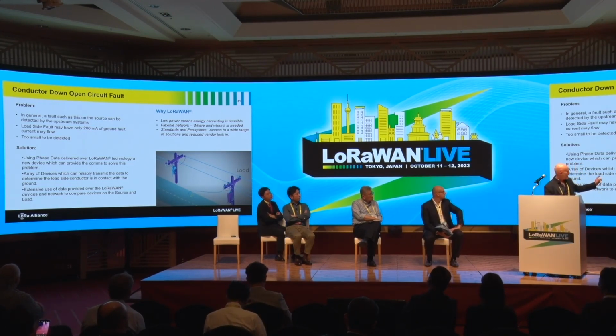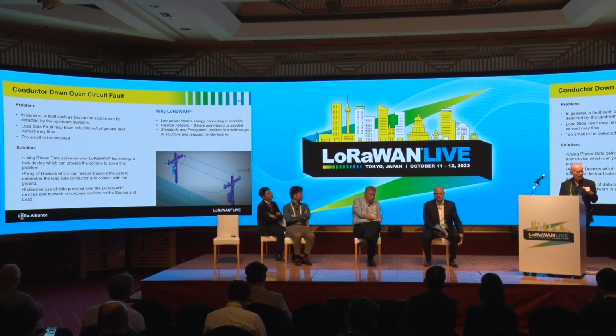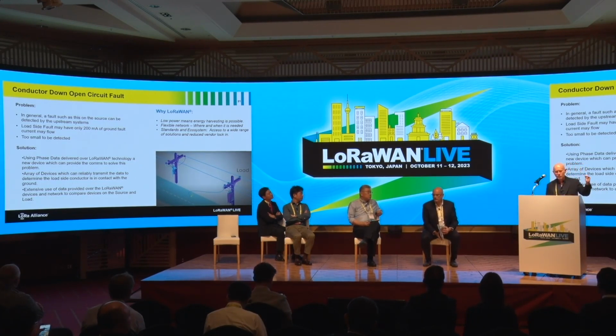But if that line down happens at the load side, in other words, downstream from the main source of power, you still get current flow because you've got backflow. It's still at 11 kV or 33 kV or 115, but the current flowing might only be 200 milliamps. That's not enough to trigger the systems at the head end, but that line is now sitting on the ground. Any person who touches it, any dog who touches it, any car that goes over it is immediately electrocuted. And there is no way to know that that system is off.